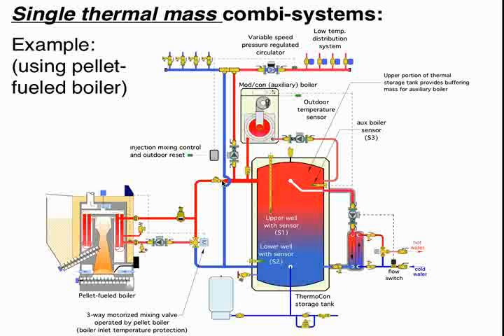If it's critical that you recover quickly from a setback, then I would say probably maintain the tank because there's energy in reserve that can quickly move out to the load. If that's not as critical, and especially if it's a smaller buffer tank, maybe 119 gallons or less, I probably wouldn't choose to maintain it, especially if the loads may be off for a day or two, because that's just standby heat loss. And anytime you're converting fuel, high-grade energy, into heat, low-grade energy, it's a race against time as far as heat loss from the tank.